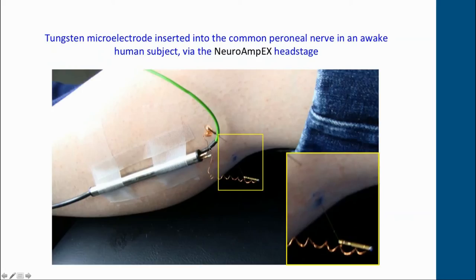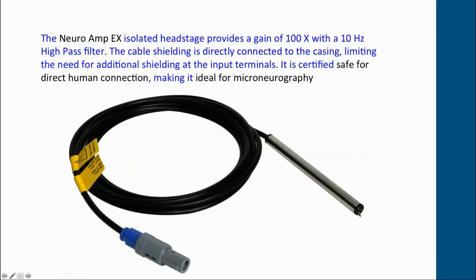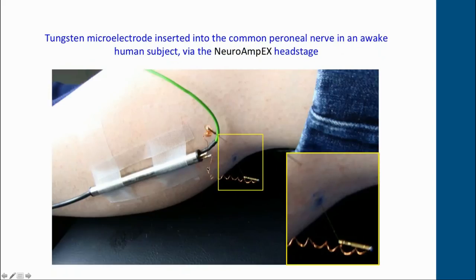The green lead is attached to a simple silver-silver chloride surface electrode — just a stick-on ECG electrode over the knee or anywhere nearby. There are two electrode terminals. One is a ground lead and, as this is a differential amplifier, one input is positive and the other is negative. We have a microelectrode inserted into the common peroneal nerve. The blue mark simply indicates the site over the nerve defined as the best site for inserting.